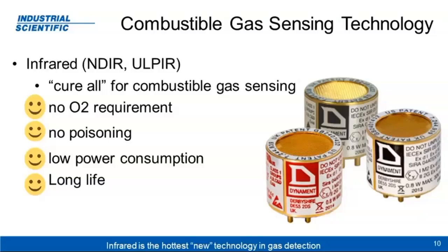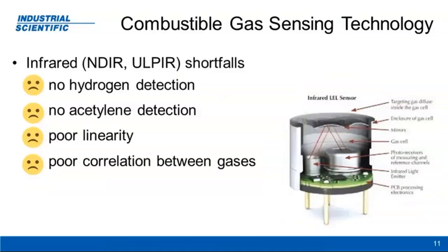But as I said, they're not the cure-all that everyone thinks they are, and there's certainly some pitfalls to using infrared sensors. The first is they don't detect hydrogen. Often misunderstood in many of the applications you run into. The first question, are you going to have any possibility of encountering hydrogen? And if you do, then the infrared sensor has to be out. We can't detect acetylene or other compounds where the infrared absorption isn't as strong, or it doesn't fall within the absorption band of the sensor.